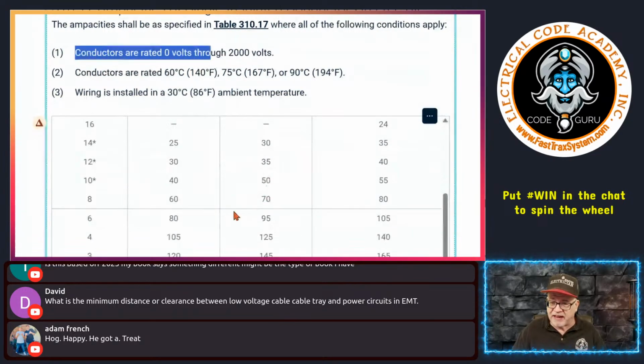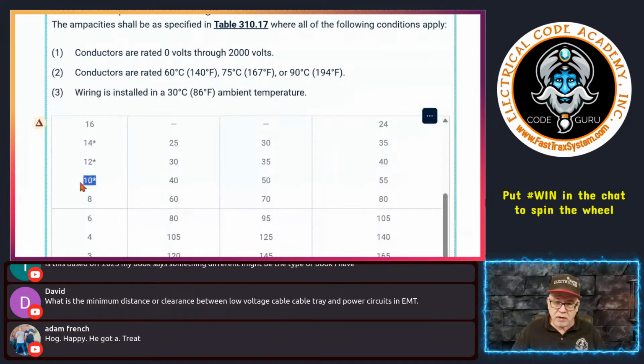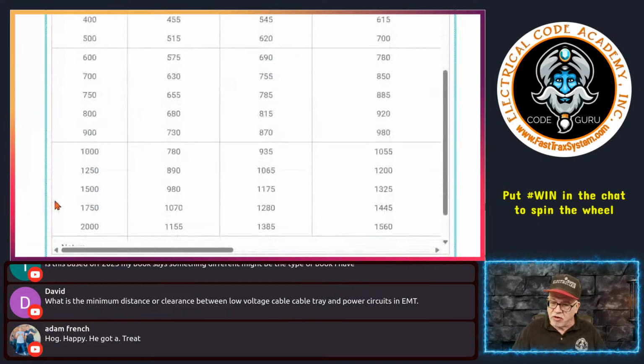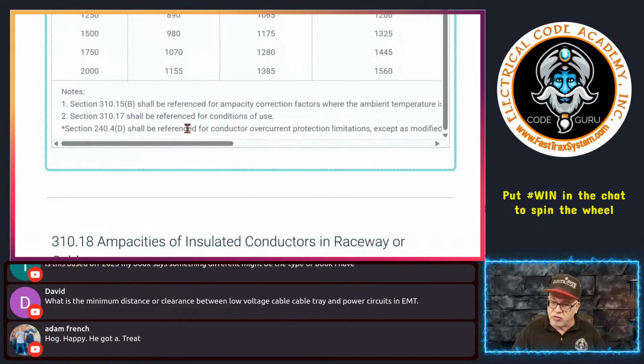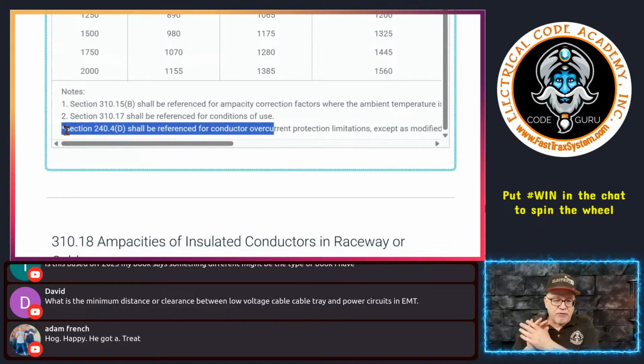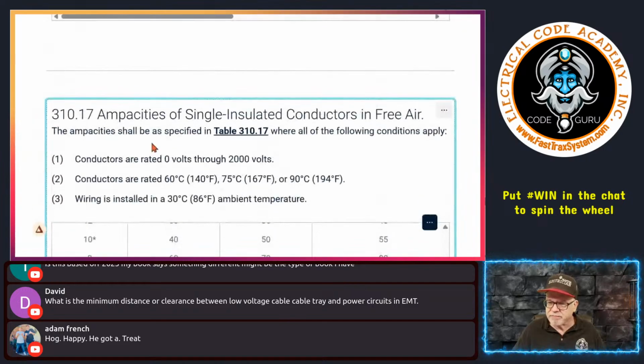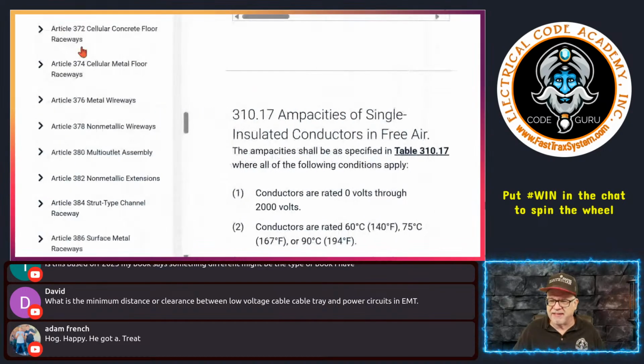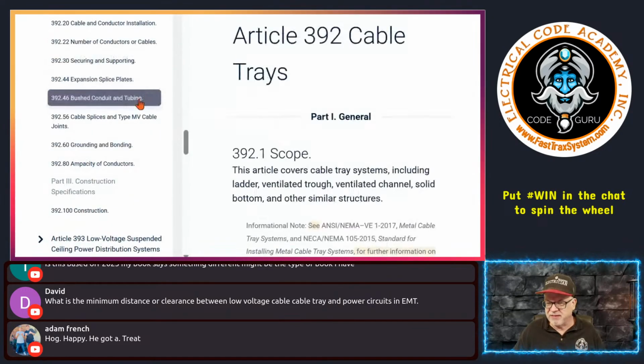And I will emphasize it. For example, look at this 10 gauge. It's 50 amps. Now, don't forget there's still an asterisk. The asterisk is still going to limit you to the small conductor rules, by the way. So don't ever lose sight that you're still going to have to follow the terminal limitations and things like that in 110.14(C). So don't get all excited. You still have to follow the rules. But at the end of the day, you can do it from this higher ampacity. And let me see if it gets me back where I'm at.